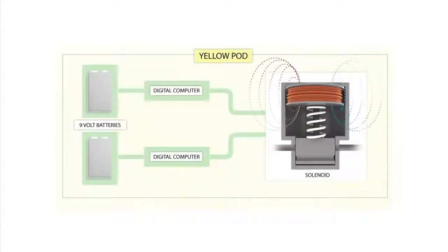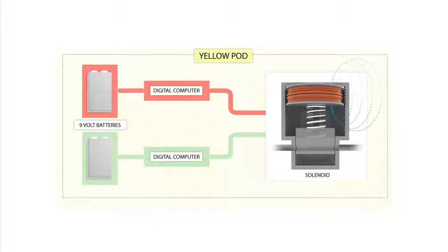Only a third unplanned failure allowed the Yellow Pod to operate. On the night of the accident, one of the nine-volt batteries that powered the solenoid valve's computer had failed. As a result, the affected computer system could not initiate the command to energize the miswired coil. Had both coils of the miswired solenoid valve been energized, the two coils would have generated opposing forces on the valve. The solenoid valve would have remained closed, and the blind shear ram would never have been closed. However, the failed battery rendered one coil inoperable, and most likely allowed the other coil to open the solenoid valve by itself.